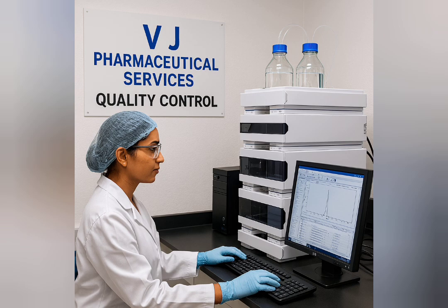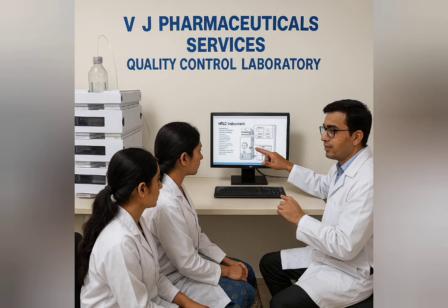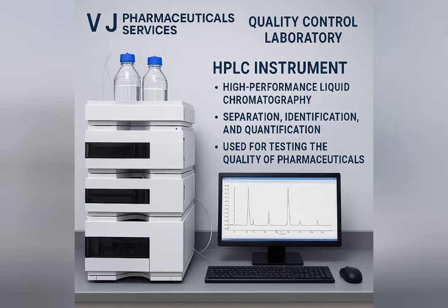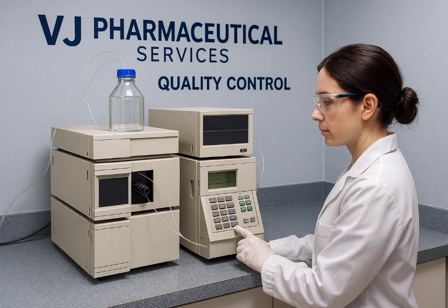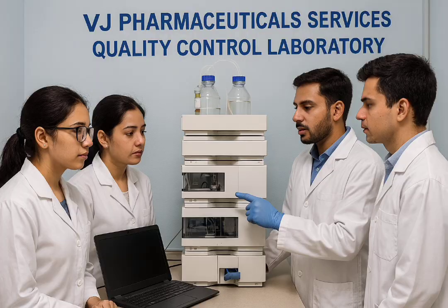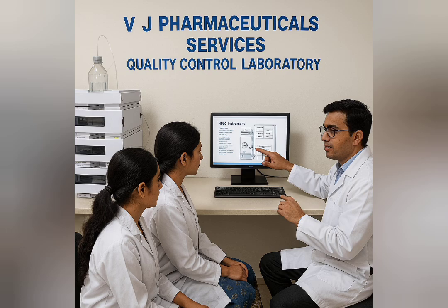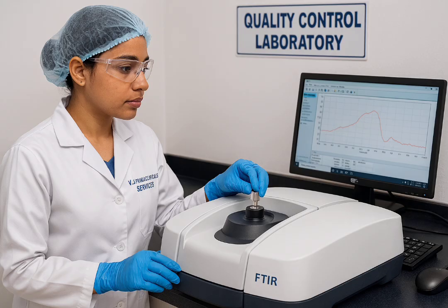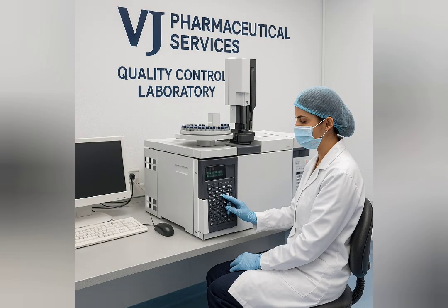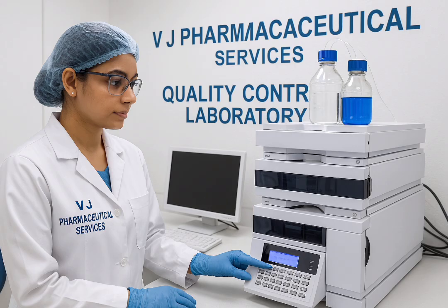Introduction to HPLC. High-performance liquid chromatography, HPLC, is a process of separating components in a liquid mixture. A liquid sample is injected into a stream of solvent, the mobile phase, flowing through a column packed with a separation medium, the stationary phase. Sample components separate from one another by a process of differential migration as they flow through the column. As bands emerge from the column, flow carries them to one or more detectors which deliver a voltage response as a function of time. This is called a chromatogram. For each peak, the time at which it emerges identifies the sample constituent with respect to a standard. The peak's area represents the quantity.